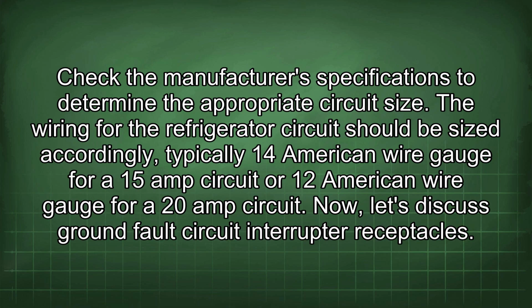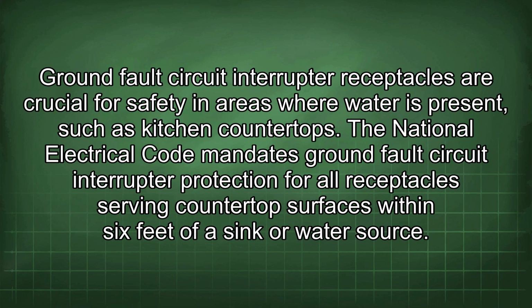The wiring for the refrigerator circuit should be sized accordingly, typically 14 American wire gauge for a 15 amp circuit or 12 American wire gauge for a 20 amp circuit. Now let's discuss ground fault circuit interrupter receptacles. Ground fault circuit interrupter receptacles are crucial for safety in areas where water is present, such as kitchen countertops.